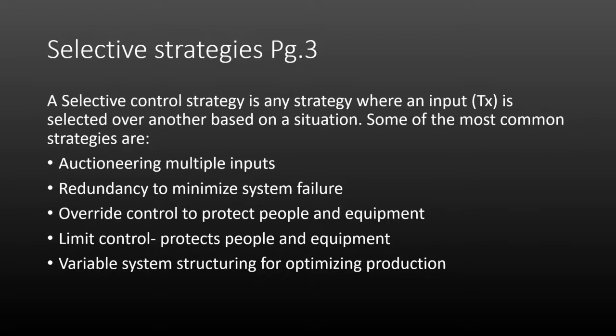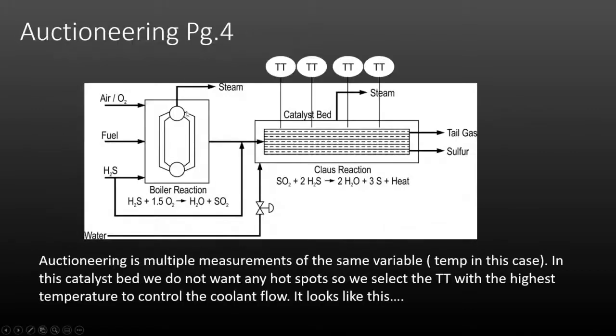Limit controls are put in place to protect people and equipment — you'll see limit controls quite a bit on furnace type systems. The last one is called variable system structuring for optimizing production. The first application is auctioneering. Here we have a reactor bed or catalyst bed where we take temperatures across the bed. The auctioneering function takes multiple measurements of the same variable — in this case, the temperature of the reactor bed.